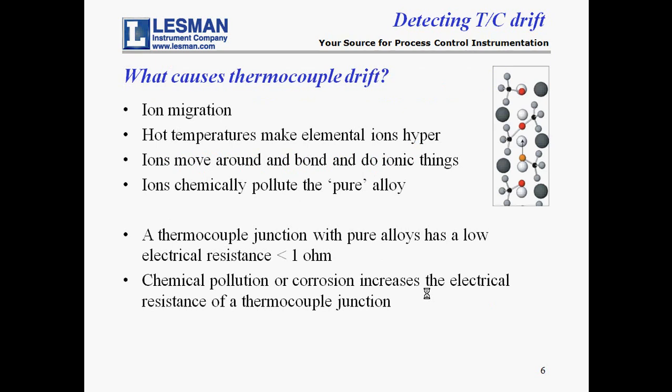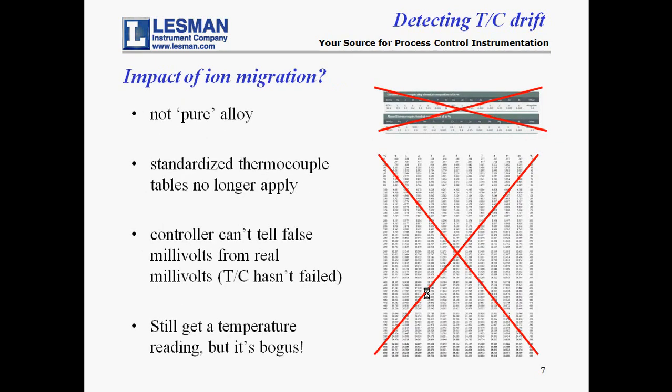Thermocouple drift is caused by ion migration, a form of corrosion. High temperatures excite ions in the protection sheath, the protection tube, or the atmosphere. These excited ions mix with the alloy metals, polluting the pure alloys at the thermocouple junction. The hotter the exposure temperature, the more quickly the ions pollute the alloys. The chemical change in the alloy metals also produces increased electrical resistance at the junction. In the K-type thermocouple example, the alloy metals are no longer pure chromel and pure alumel alloys, but are some unknown impure alloy of an unknown chemical makeup.